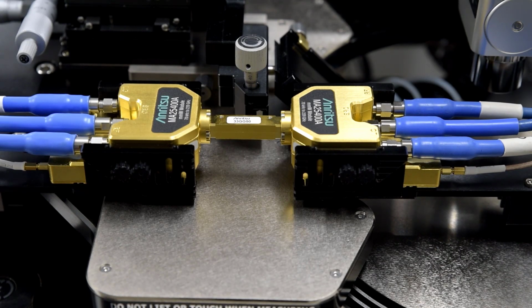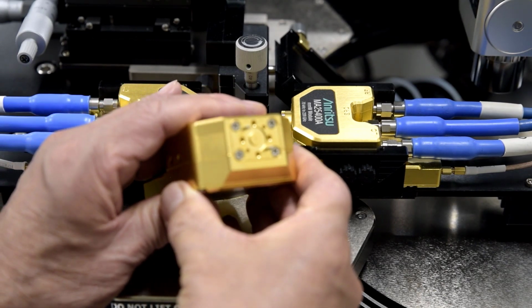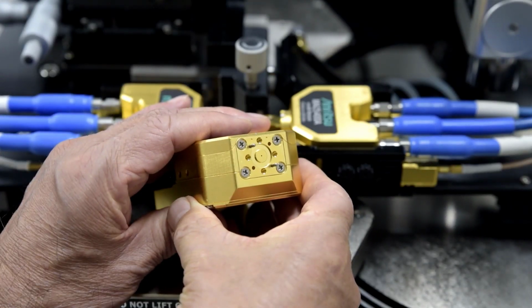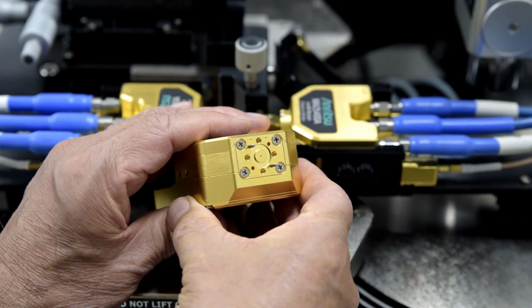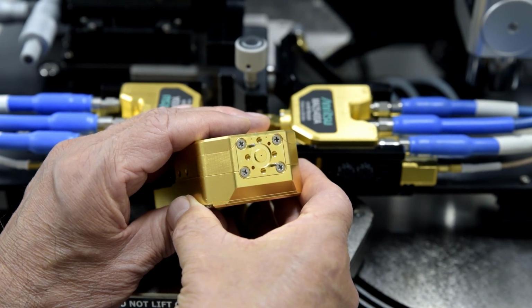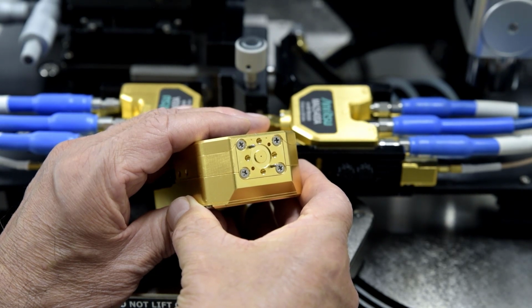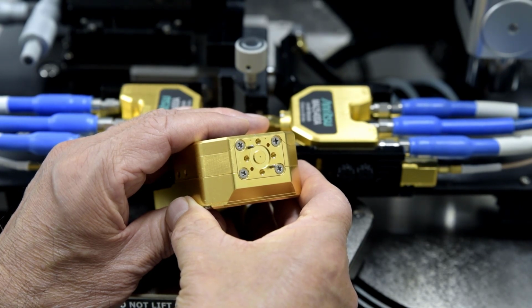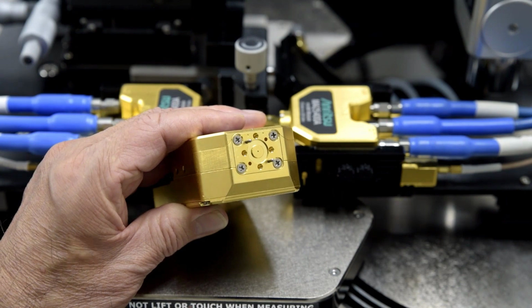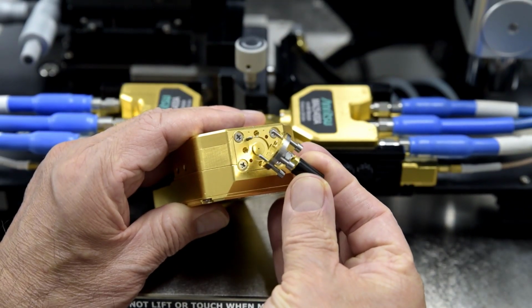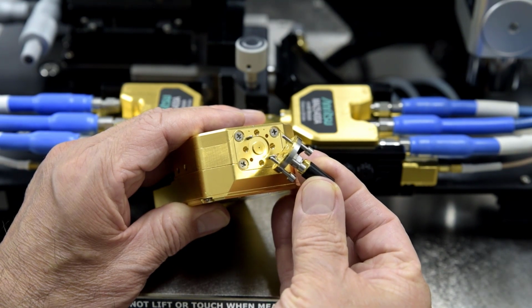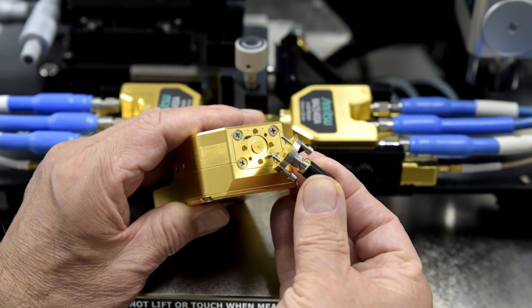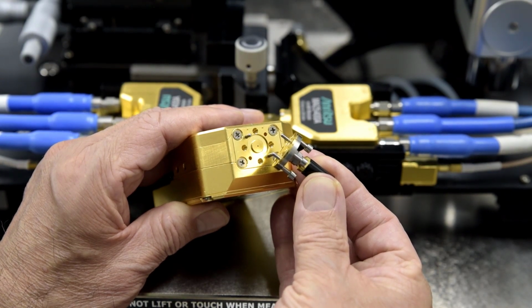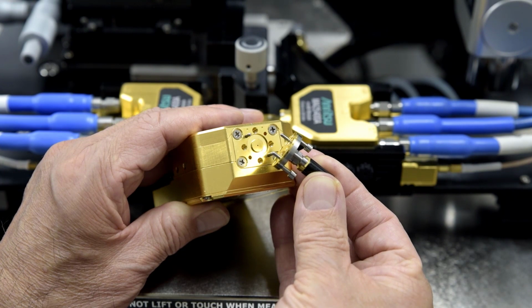If you recall, the test port of the module provides a UG387 flange adapter, and the pins of that flange is what provides guidance for the coaxial pins and will ensure that they align before making the insertion. And so for the case when we were using the 0.8 short for the S11 and S22 measurements, we were connecting that to the flange adapter going to 0.8 coaxial connection.